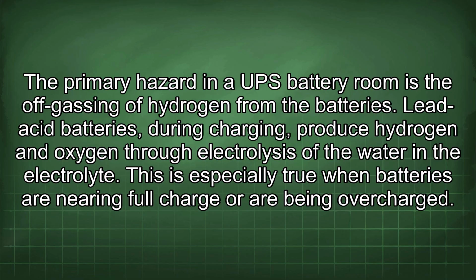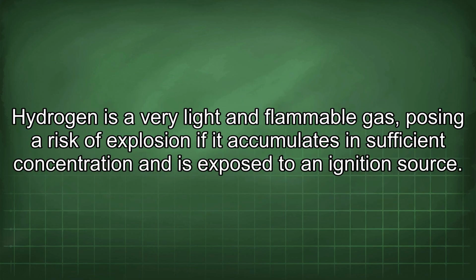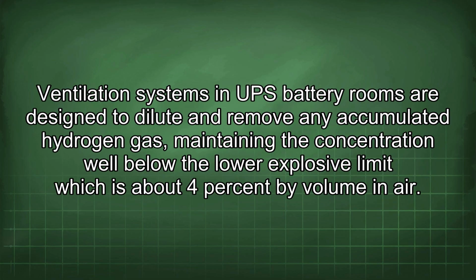The primary hazard in a UPS battery room is the off-gassing of hydrogen from the batteries. Lead-acid batteries, during charging, produce hydrogen and oxygen through electrolysis of the water in the electrolyte. This is especially true when batteries are nearing full charge or are being overcharged. Hydrogen is a very light and flammable gas, posing a risk of explosion if it accumulates in sufficient concentration and is exposed to an ignition source. Ventilation systems in UPS battery rooms are designed to dilute and remove any accumulated hydrogen gas, maintaining the concentration well below the lower explosive limit, which is about 4% by volume in air.